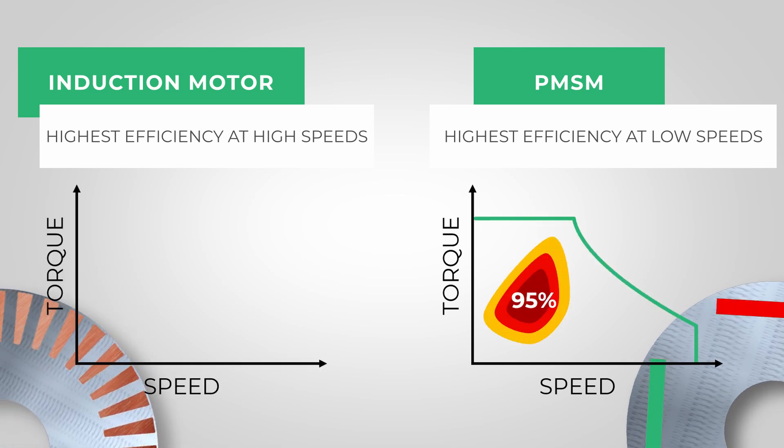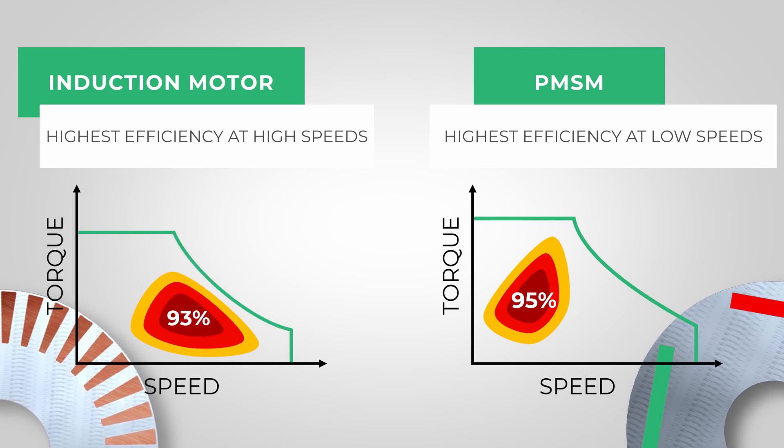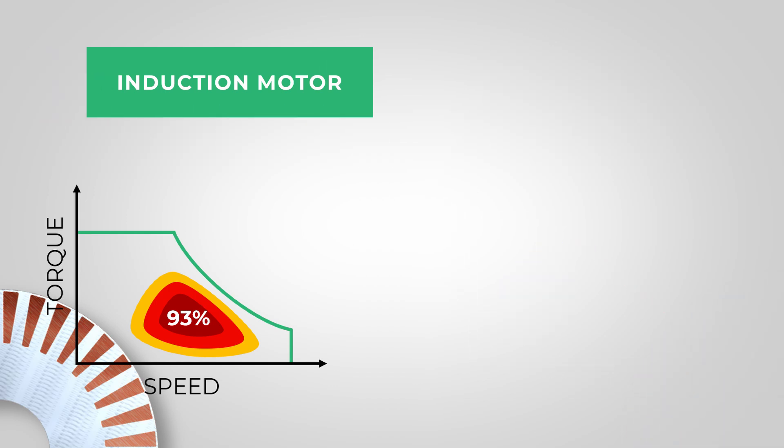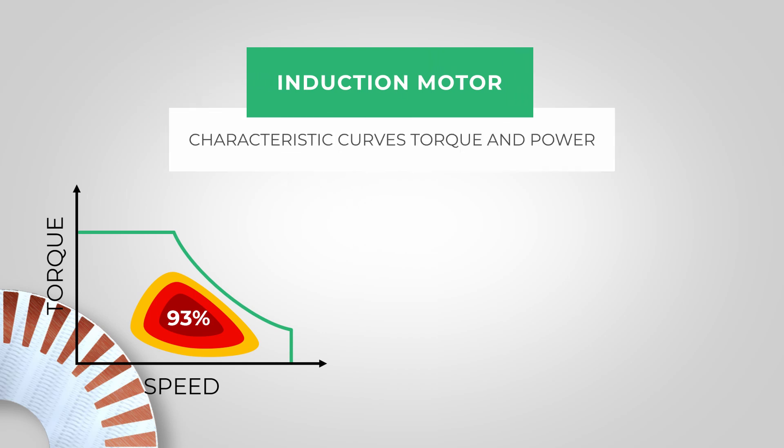However, induction motors achieve a slightly better efficiency at high speeds compared to a conventional PMSM. This is because an additional current is needed for the PMSM to weaken the magnets in the higher speed range. But exactly at high speeds, a very good efficiency is very important because here the power or the energy consumption is very high.